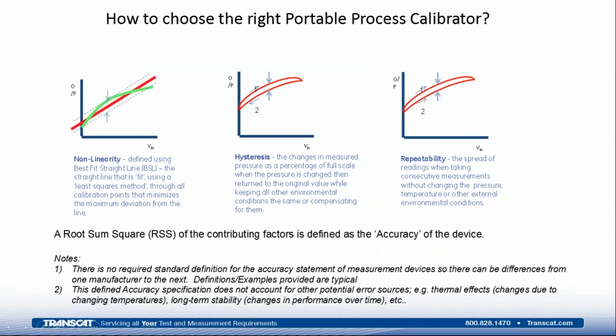So nonlinearity: every device has an output and there is no perfect device. So it's rare, never, the case where the output of a device is perfectly linear, exactly what you would expect as an output for a given input. So we have to define the nonlinearity or the level of nonlinearity. So we define it typically using the best fit straight line as I referred to before, and that's the straight line that is fit using a least squares method through all of the calibration points that minimizes the maximum deviation from the line. That's the way we define it.